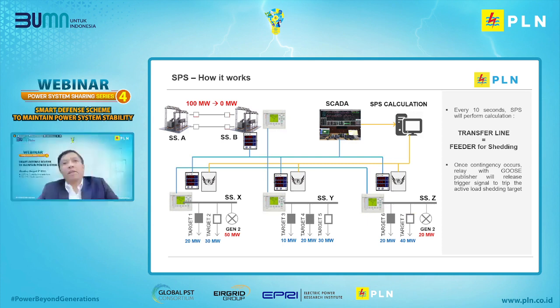Let's say the transfer condition is 100 megawatt, several feeders will be selected with a total load approximately equal to 100 megawatt. Then the SPS server will send a ready signal to the selected targets. When there is a disturbance that causes the transfer to become 0 megawatt, the SPS relay will send a GOOSE signal which will initiate the tripping of the shedding targets that SPS has prepared.